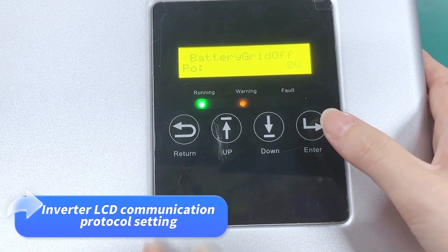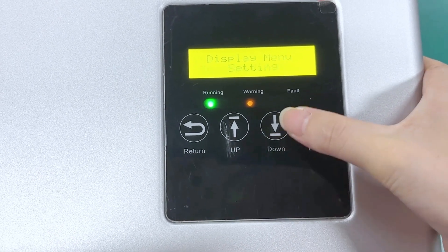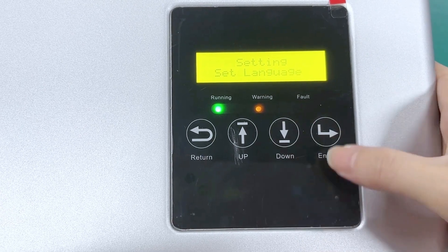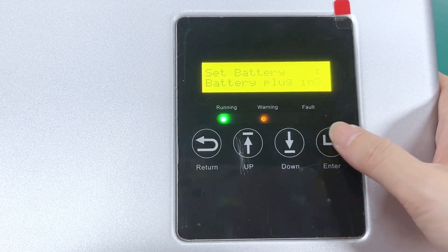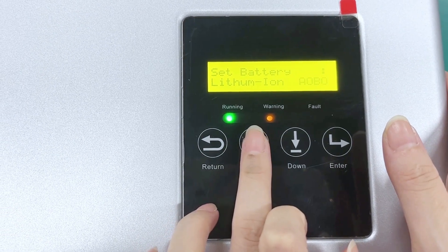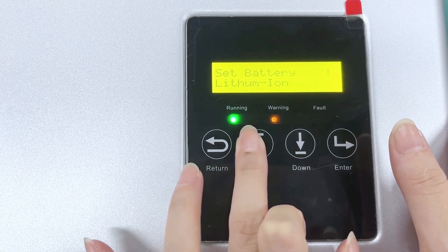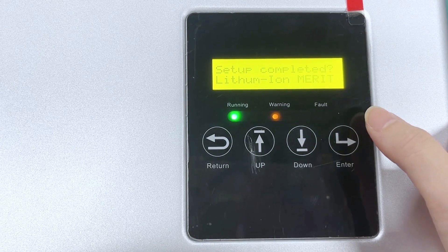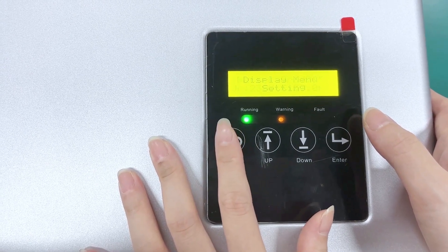We can now set up on the LCD of the inverter. Press and hold Enter to access the settings page. Find 'Setting > Set Battery' in the display menu and enter the battery plug-in settings. Select the battery type and choose the correct battery plug-in option for our MERIT lithium battery. The communication between the battery and inverter has been established successfully.